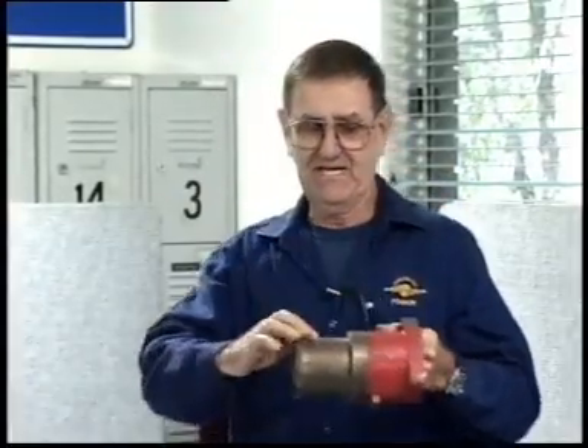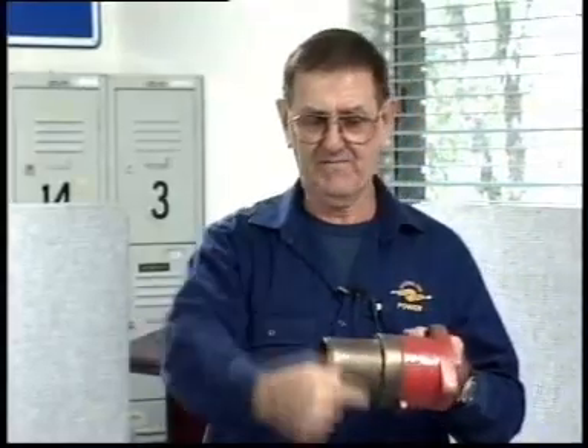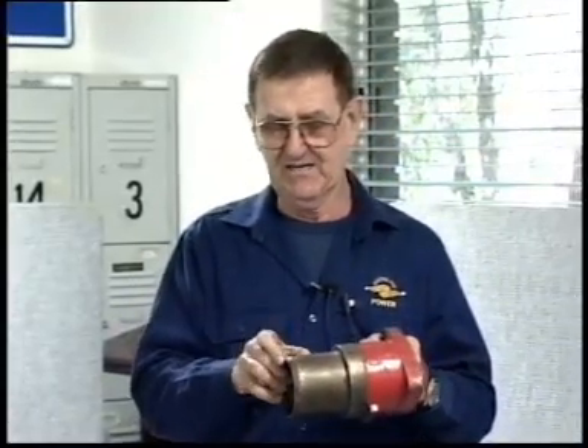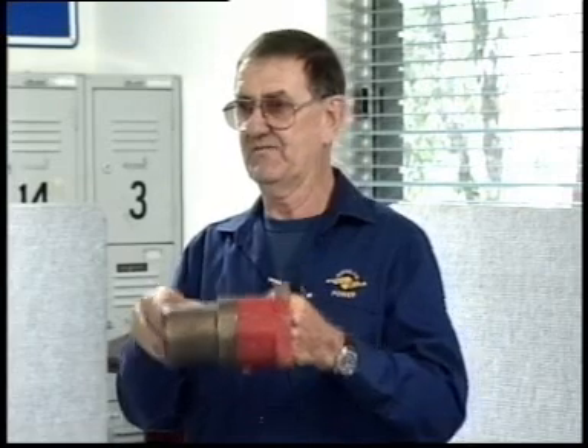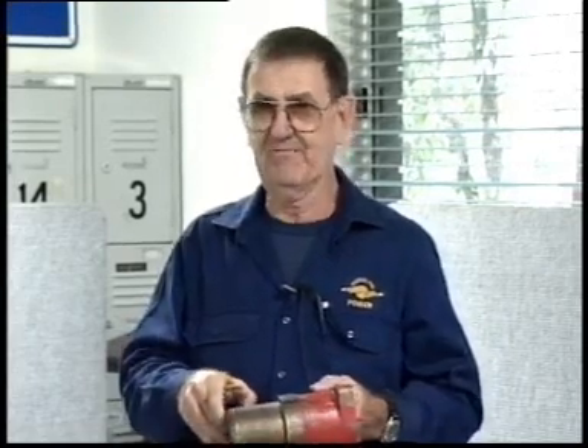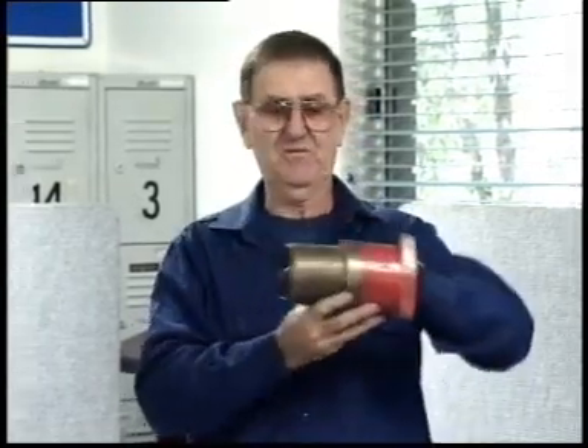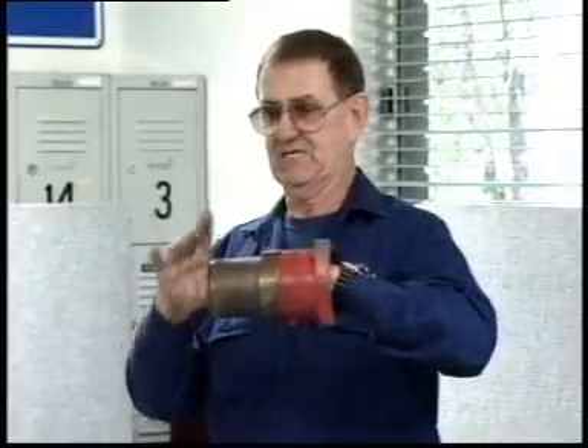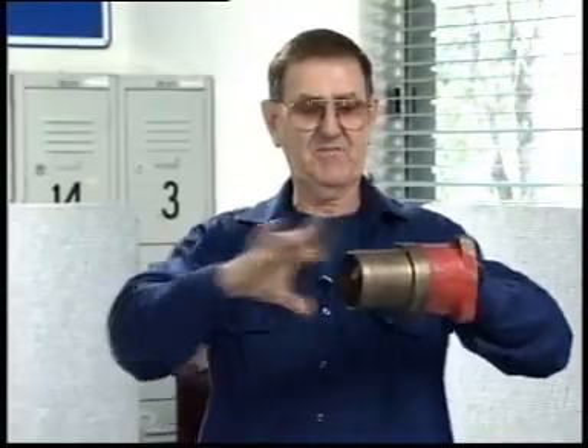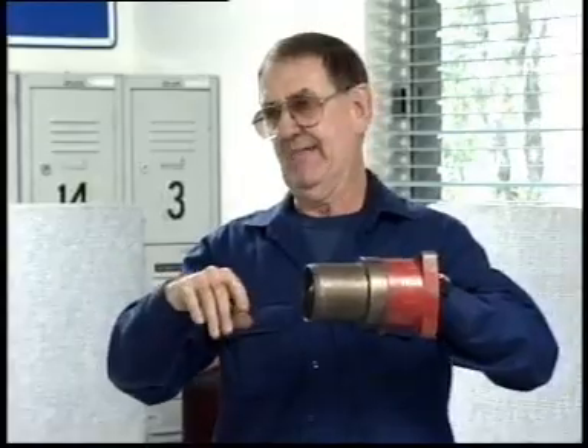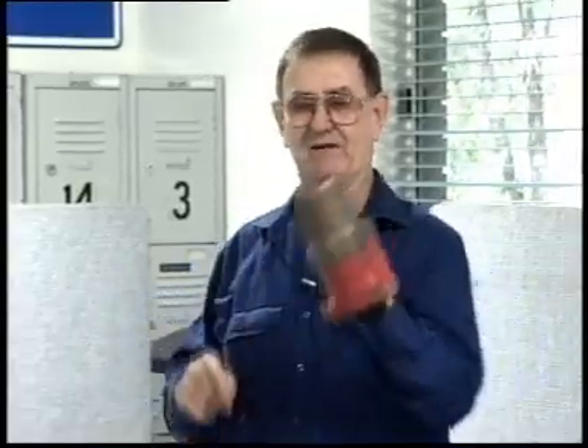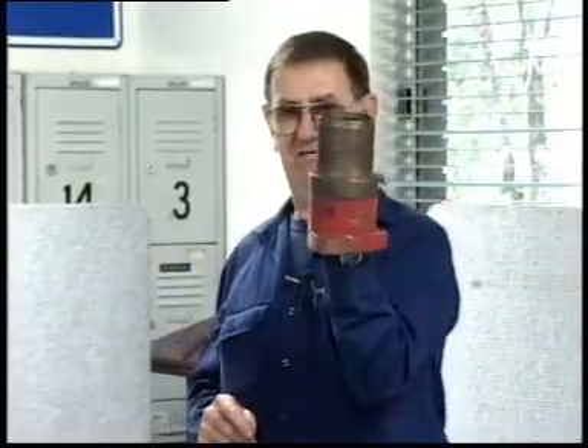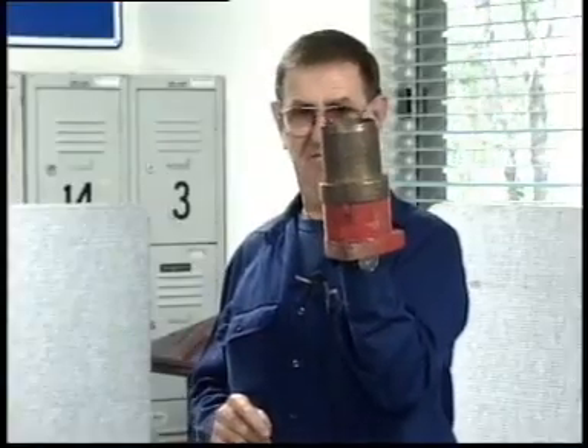This one here has a mark right around the circumference of it. It's about close to 1.5 to 2 mils wide. It's very deep, you can feel it with your thumbnail. With all due respect to everybody, that one there would pass the test, because we've got a lot of length of flame path for a flame to pass over without creating a problem. However, when we saw that, and we don't know how it was done, we decided we'd keep it as an example, that particular one. I've damaged this one here specifically. I've put a scratch down one side, which you can feel with your nail.